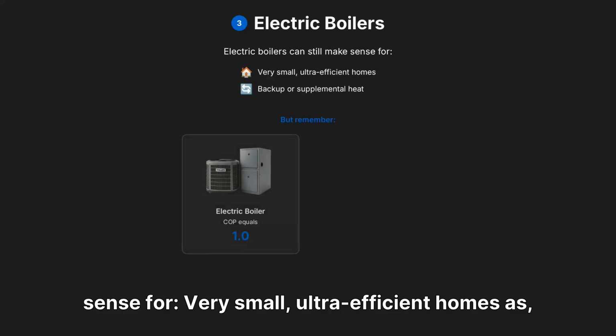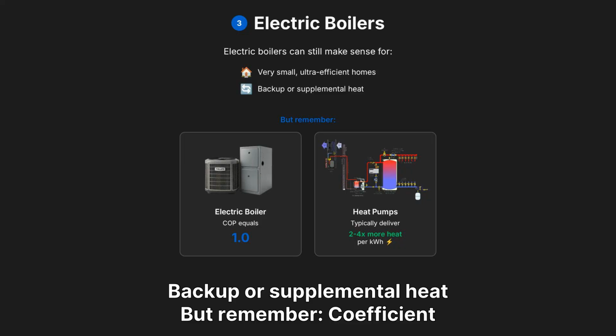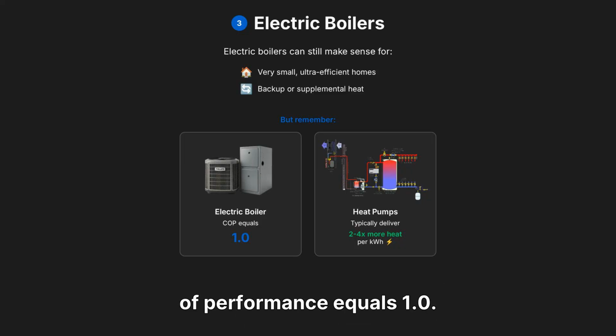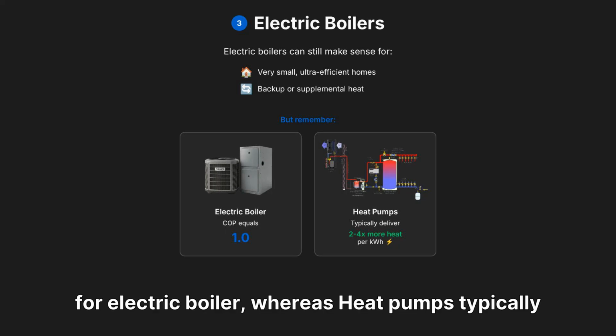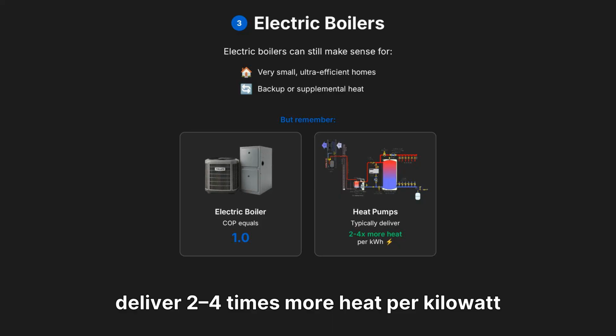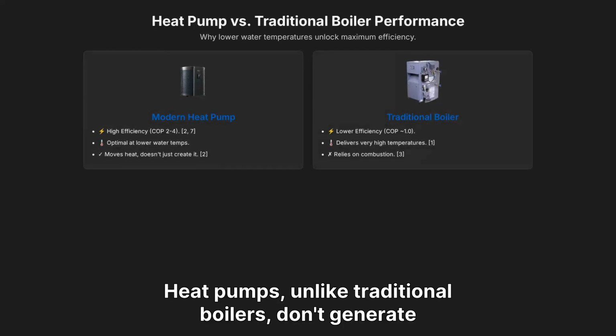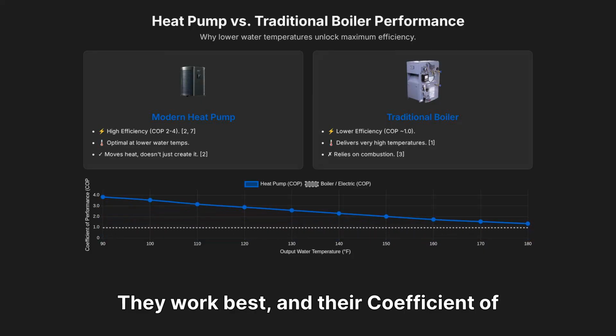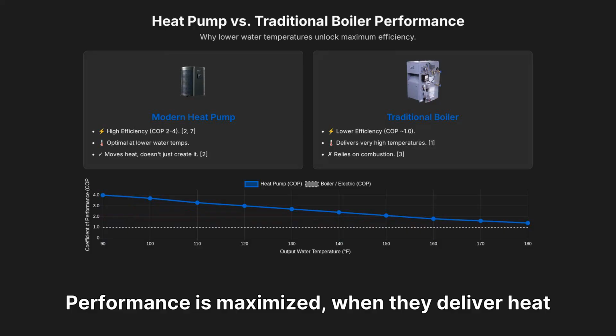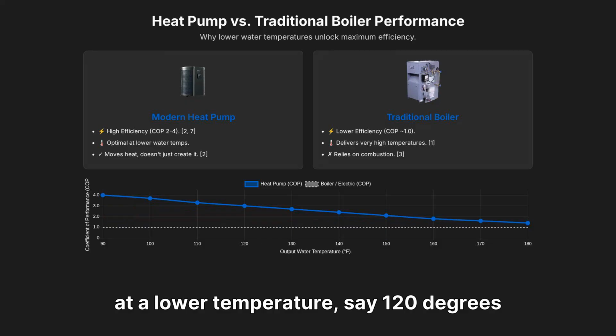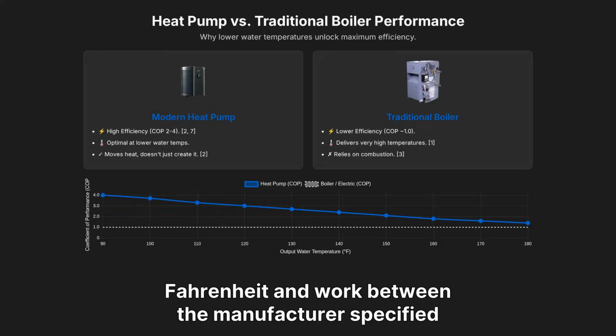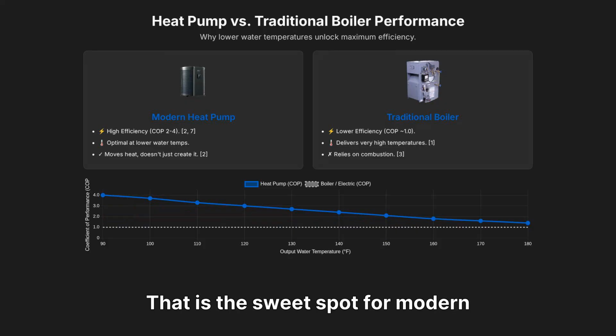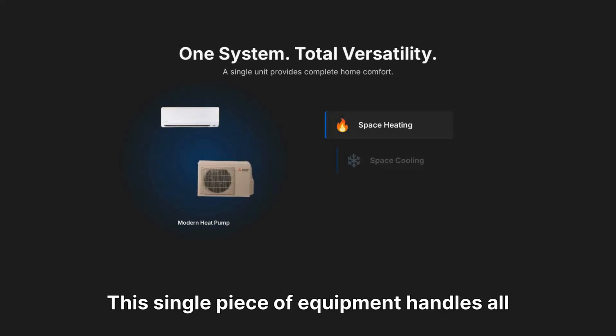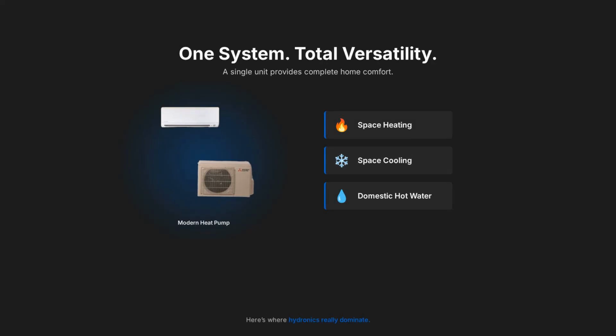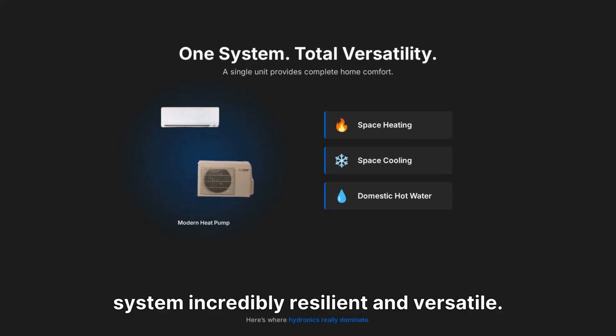Three, electric boilers. Electric boilers can still make sense for very small, ultra-efficient homes as backup or supplemental heat. But remember, the coefficient of performance equals 1.0 for an electric boiler, whereas heat pumps typically deliver 2 to 4 times more heat per kilowatt hour. Heat pumps, unlike traditional boilers, don't generate extremely high temperatures. They work best, and their coefficient of performance is maximized, when they deliver heat at a lower temperature, say 120 degrees Fahrenheit, and work within the manufacturer's specified ambient temperature range. That is the sweet spot for modern hydronic emitters. This single piece of equipment handles all your space heating, space cooling, and often your domestic hot water, making the whole system incredibly resilient and versatile.